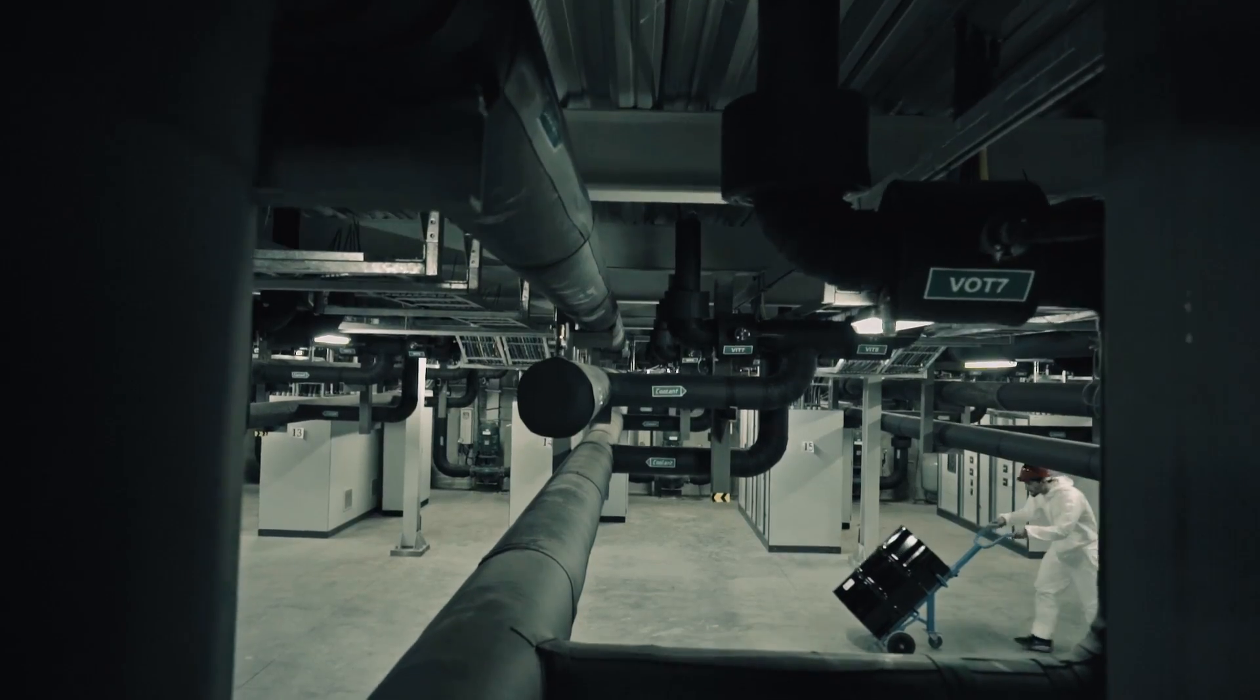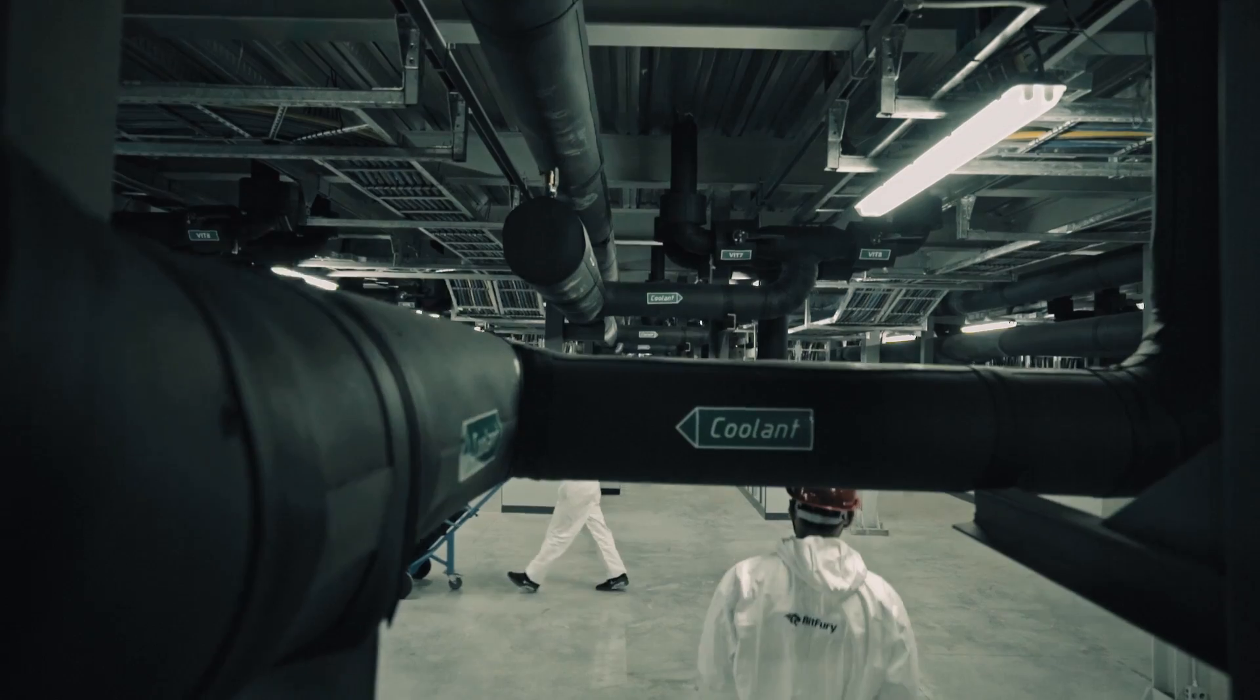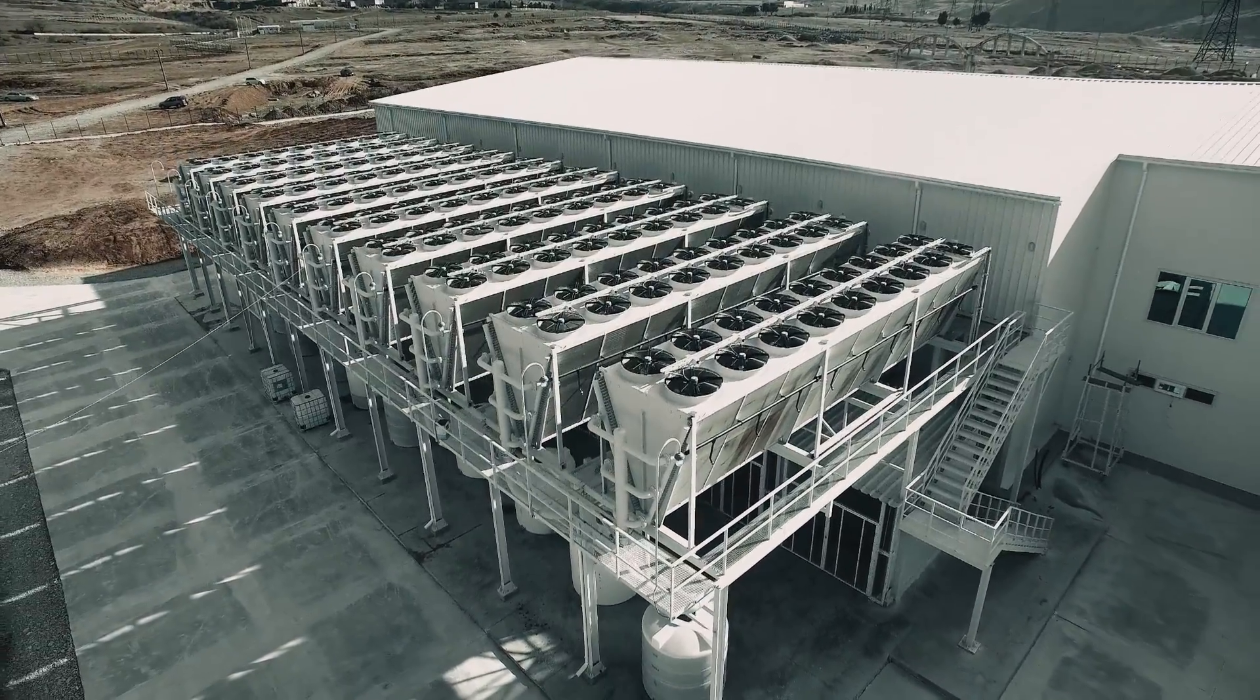The fluid is engineered to evaporate as the chips generate heat. When the Novec fluid evaporates, it rises to the top of the container, where it comes into contact with pipes containing cooled water. Upon contact with the cooled pipes, the Novec solution condenses and returns to the pool where it continues cooling the chips.